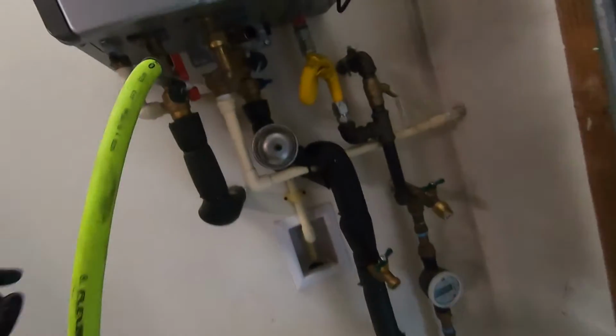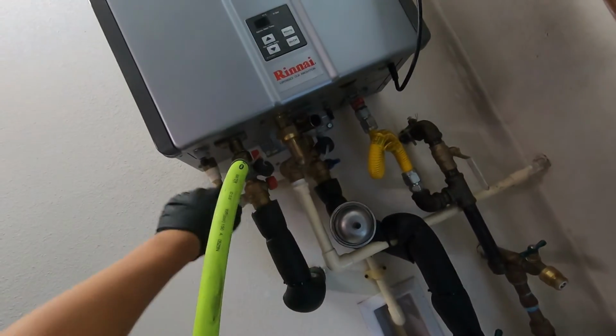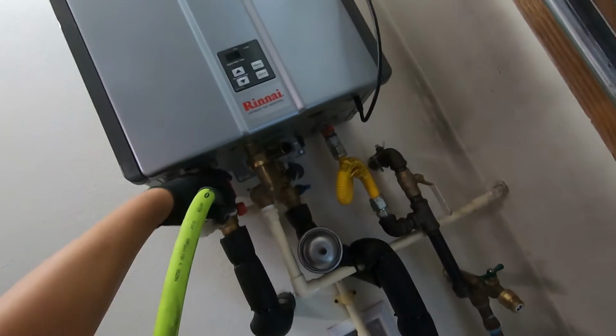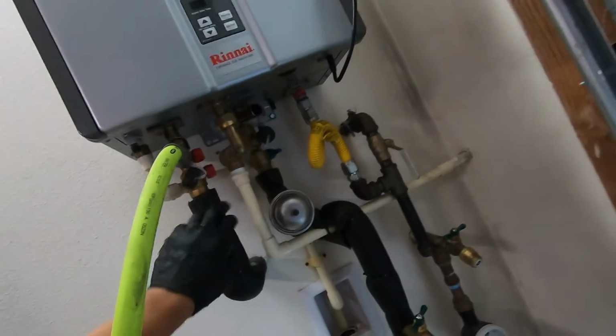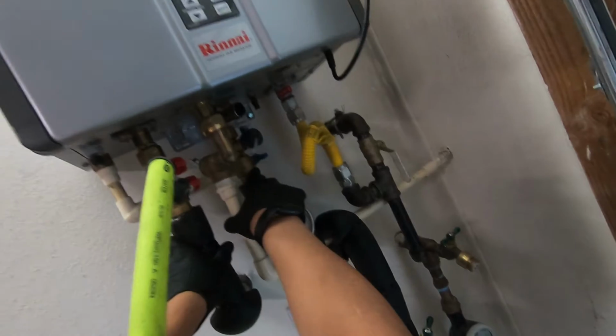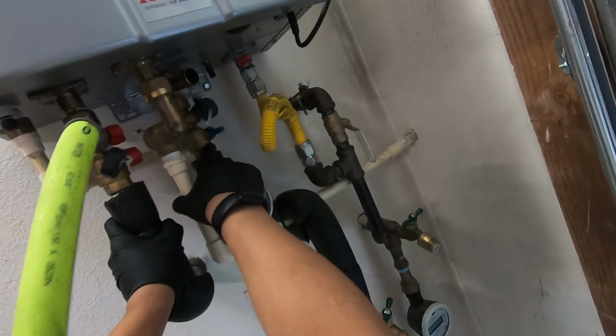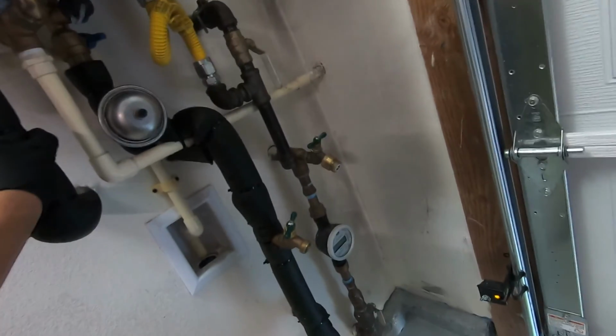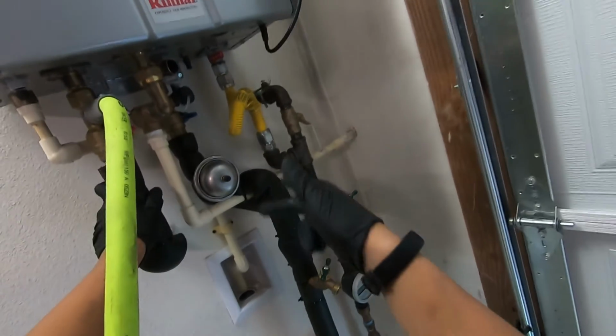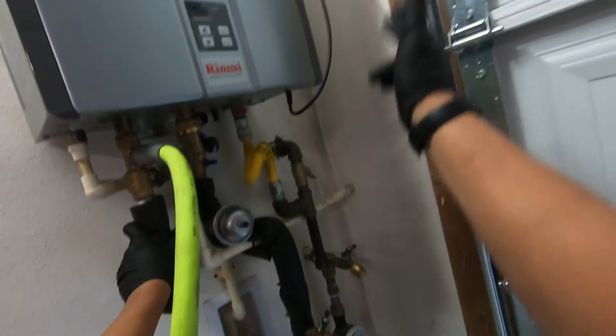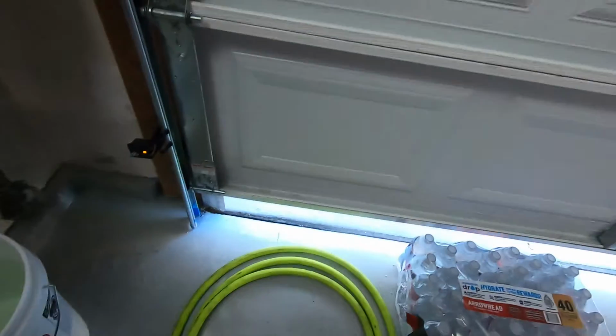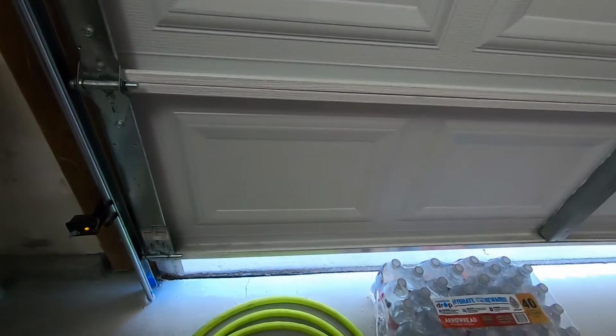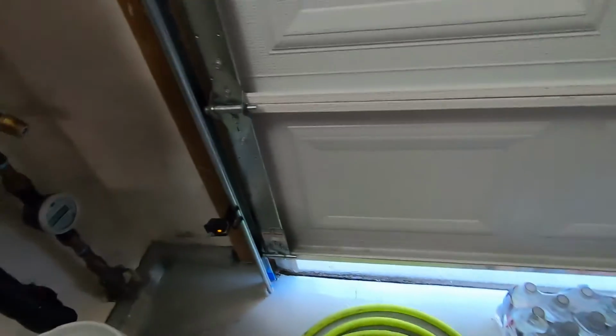Now what I'm going to do is open the valve that leads to the port on the hot side. Now we're going to turn on the cold water supply. This is going to give cold water pressure through the system, and it's going to dump and push out all the vinegar and all the debris inside the water heater out this hose. Go ahead and open that up now.